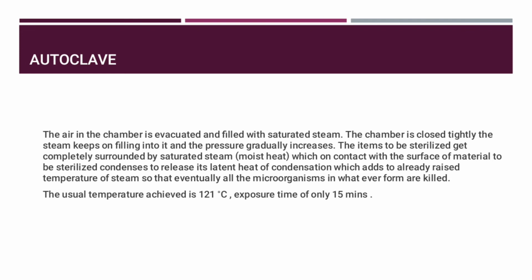The items to be sterilized get completely surrounded by the saturated steam, which on contact with the surface of the material condenses to release its latent heat of condensation, which adds to the already raised temperature of the steam, so that eventually all the microorganisms in whatever form are killed. The usual temperature achieved is 121 degrees Celsius. The exposure time is only 15 minutes.